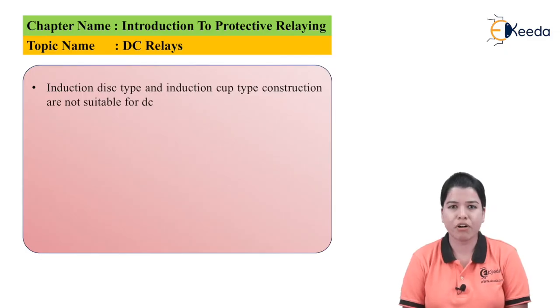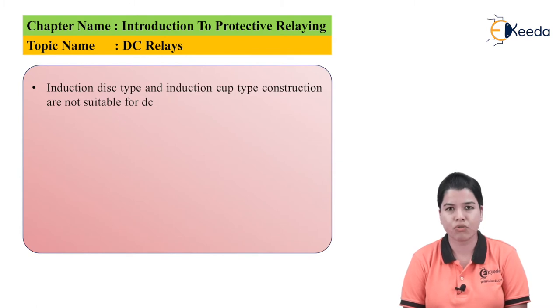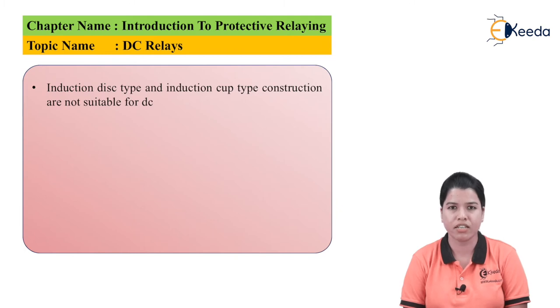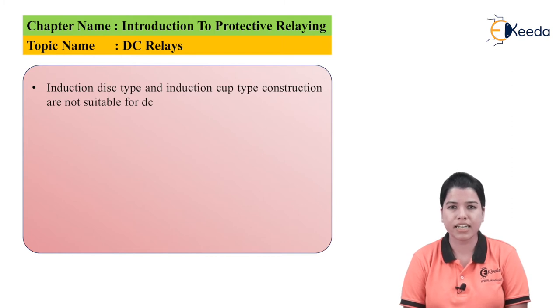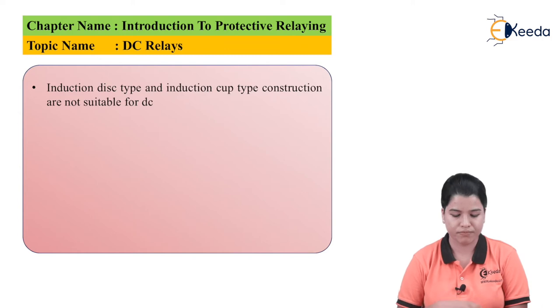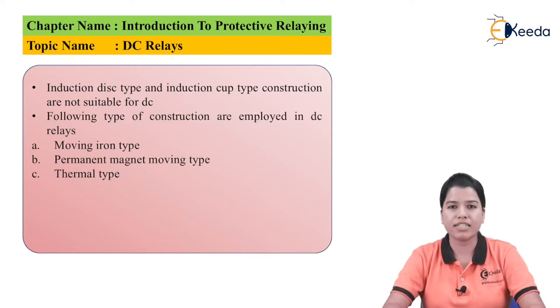The induction disc type relay and induction cup type relay cannot be used for DC quantities. The reason is that both these relays work on the interaction of alternating fluxes which produce torque. Since alternating fluxes are absent in DC, these relays cannot be used for DC.